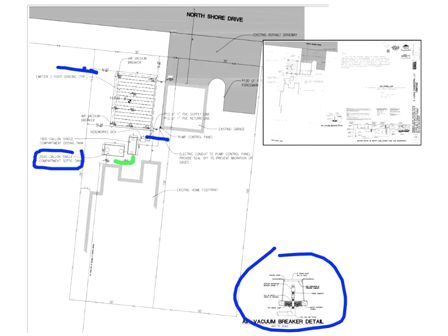Yeah, considering this, I don't know really how cold it does get on the North Shore. I would obviously include insulating information here, because this is a standard drawing without the insulating material being shown. But it doesn't mean that the designer hasn't written down the requirements for insulation.